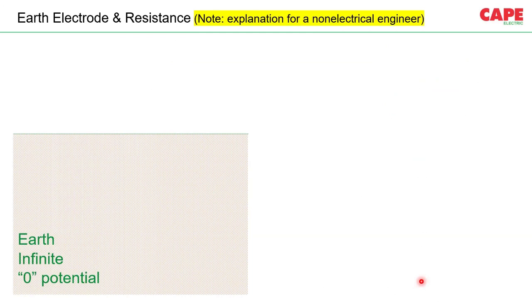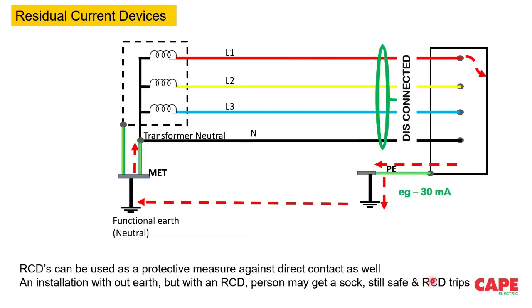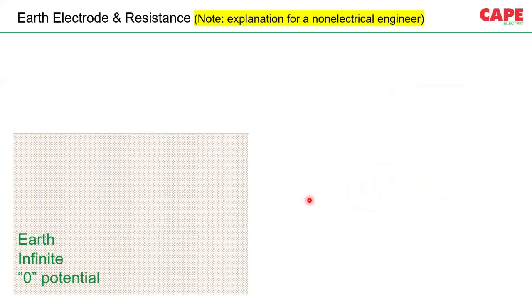Now, once we go for a TT network, we have to understand this particular mechanism. Because our idea is to understand how automatic disconnection works and the importance of the earth electrode in case of a TT network. Without understanding the method of working of the earth electrode, sometimes we will end up with trouble. I am trying to explain what the earth electrode is and how it has to work in a low voltage TT network.